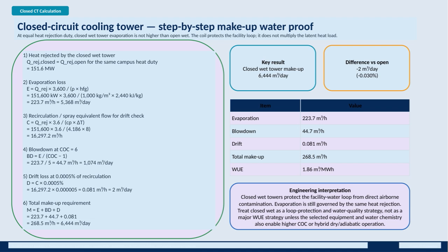First, we note that for the same heat rejection duty, the closed wet tower's evaporation loss is essentially the same as an open wet tower. This is because the coil protects a facility loop but doesn't increase the latent heat load. Starting with heat rejection, the closed tower rejects 151.6 megawatts, identical to the open system. Using this, we calculate evaporation loss, which comes out to 223.7 cubic meters per hour, or about 5,368 cubic meters per day.